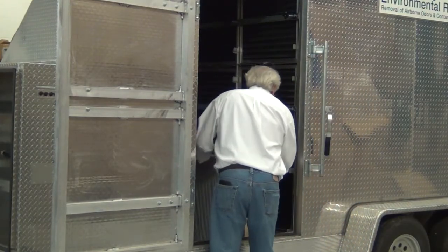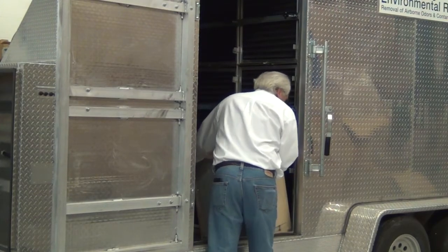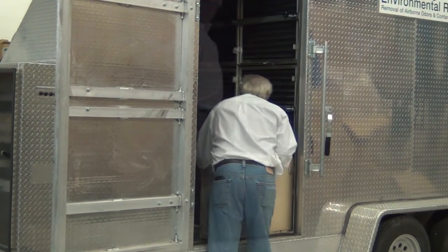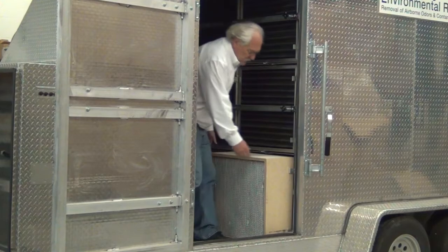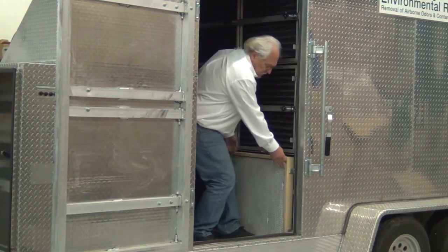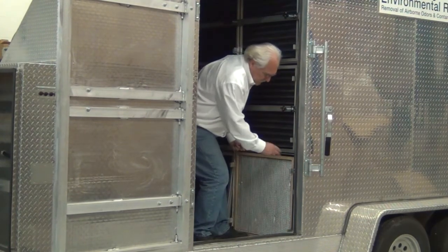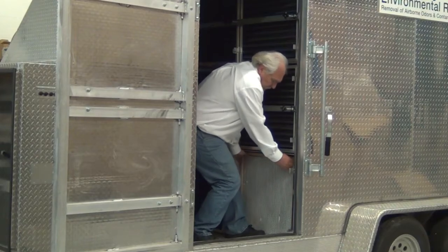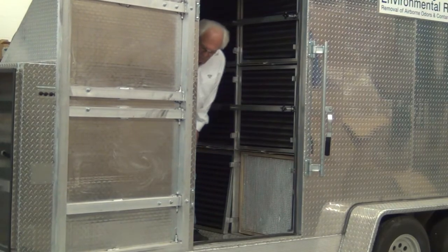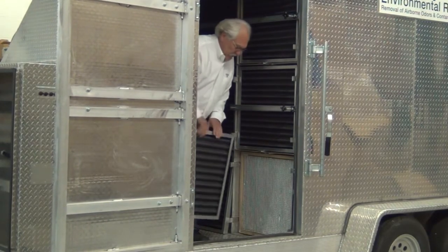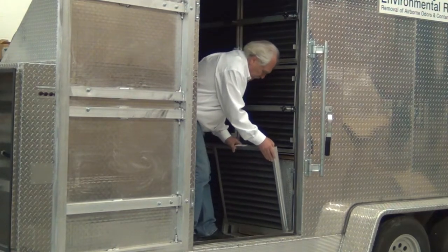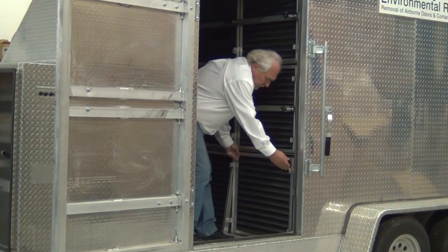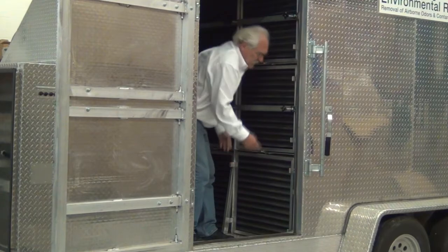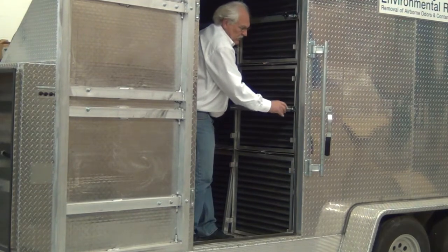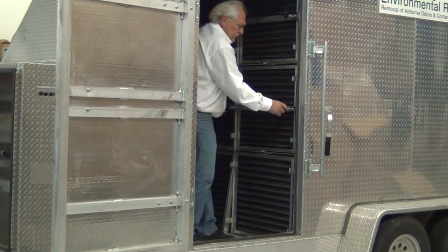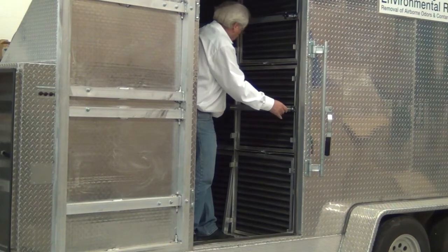The HEPA filter slides into the frame first, and the rear seal seals against the back of the filter. The MERV 13 filter then operates as a pre-filter, and it slides in front. The filters are held in place by this bar and these tightening fittings.